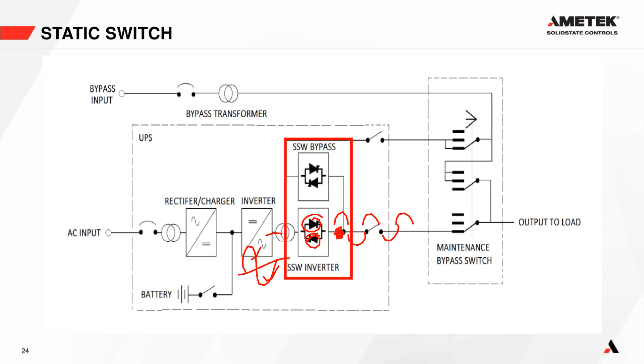So we have to do something about that, because a static switch has to allow both sides of the waveform through. Our output here is a sinusoidal waveform coming out of the inverter, and both sides need to get through the static switch. So we don't just have one SCR, which would only allow one portion through; we have two SCRs that allow the other side through. And I'll explain how we do that.